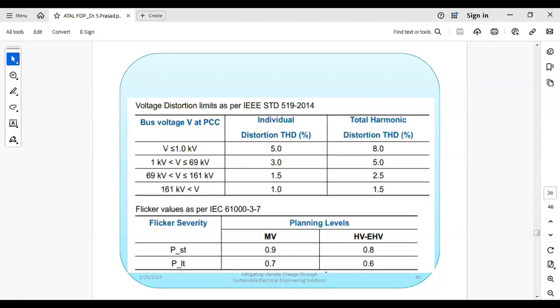If the voltage at the point of common coupling is less than 1 kV, then the acceptable total distortion is 5%. And there is total harmonic distortion and individual harmonic. This is individual harmonic because harmonic orders start from second harmonic up to 50th order. At the individual level also you have to check the percentage of second harmonic, third harmonic, fifth harmonic, seventh harmonic, up to the 50th harmonic.